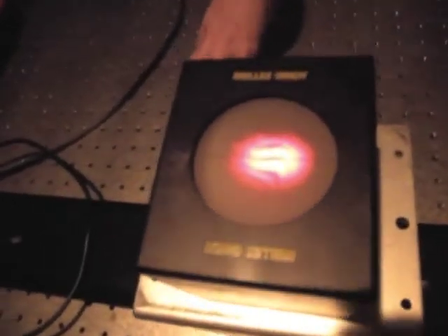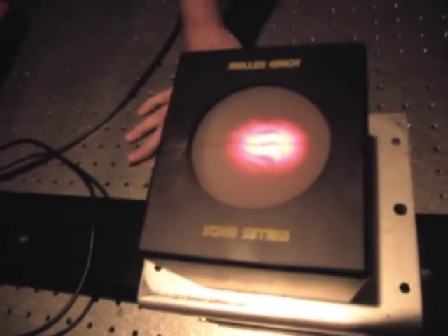Okay, so here we placed a shear plate behind our collimated laser beam. So what we can see here is some interference fringes caused by a piece of glass inside the box, which has some wedge in it, and so we have a different optical path length from the reflection off the front surface and the rear surface of the glass, and that's what causes these fringes. So we can see here a sort of cubic shape on the fringes, which is indicative of spherical aberration in our lens. And so basically we've put the collimating lens the wrong way around.